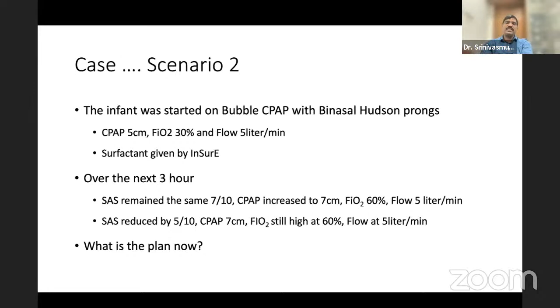So the plan in this baby would be to check for leaks. Bubbles are seen, bubbles are good, no leaks in the circuit. Bubbles are heard in the chest, air is reaching the lungs. Humidification: no condensation in the inspiratory limb, some condensation in the expiratory limb. The nasal interface should be snugly fitting. Mask or Hudson prong snugly fitting. Ram's cannula, some leak around the nostril should be there. Seal should be appropriate. Fixation should be appropriate. The prong should not be hurting the baby. The weight of the prong should not be on the baby's nose. So you need to support the tubings, as seen in the video, with some amount of gauze or a bed sheet tied up, and then give a support to the interface.